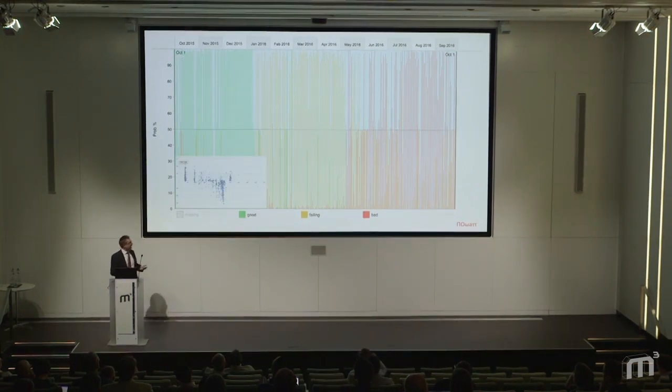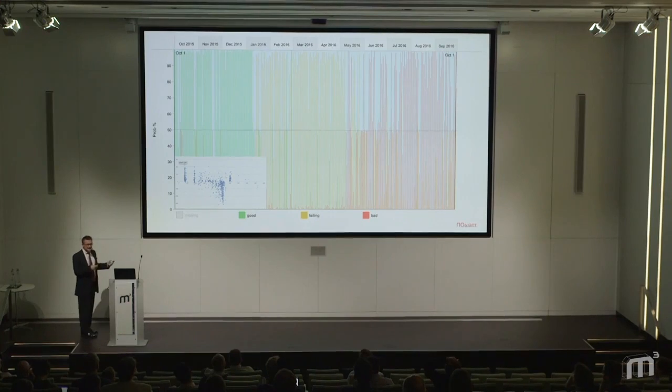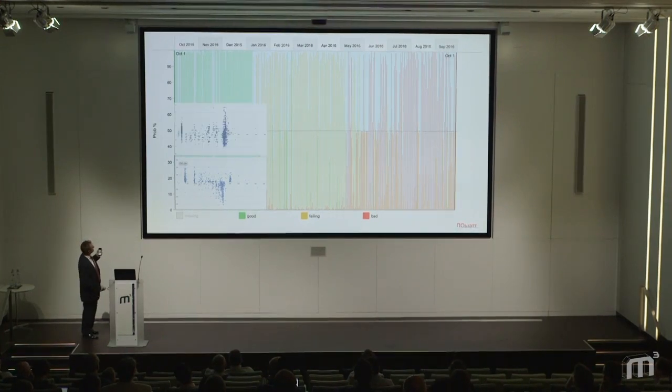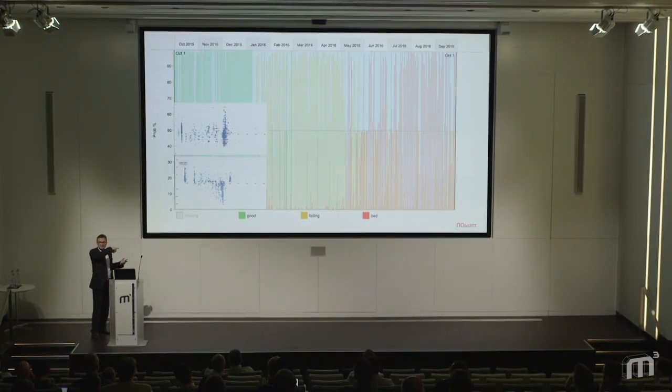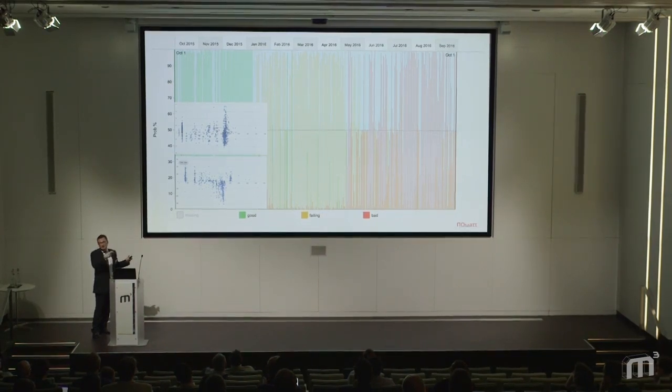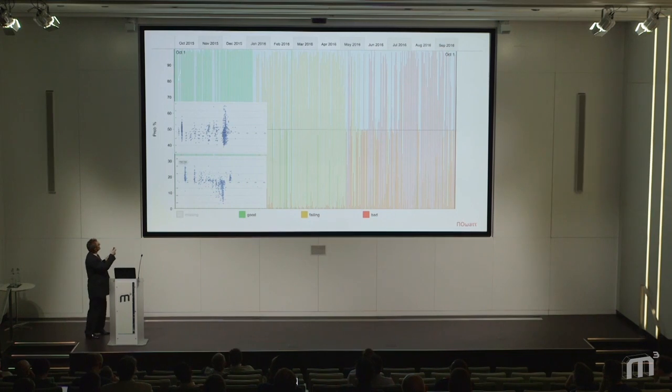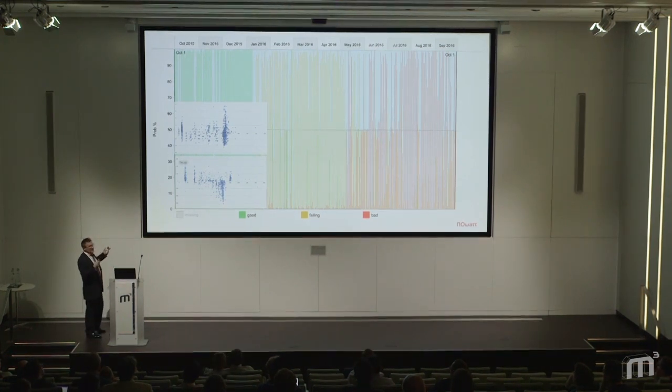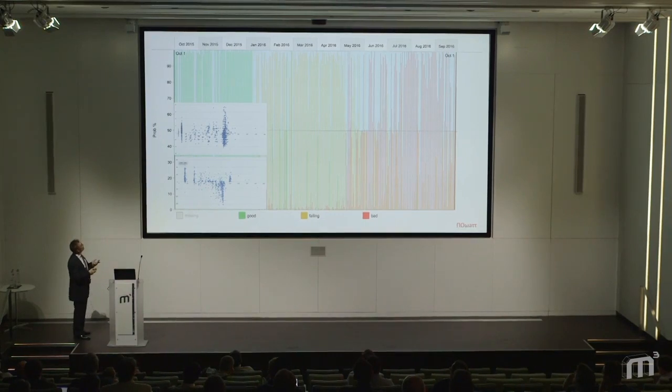Let's look at the second order pattern. Well, I think we've seen this before. If you remember the freezers I showed you, there's a lot of correlation between the freezer second order pattern and the chiller's second order pattern. They're both heat pumps. So we expect this type of thing. But see, that's how the AI can, maybe never having seen this chiller, immediately see that pattern to be good.